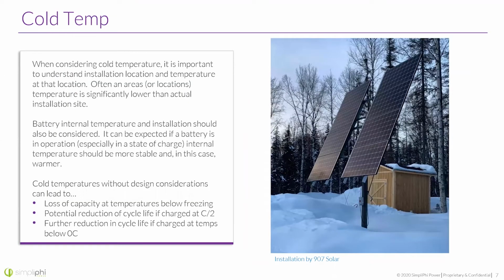So when considering cold temperature, it is important to understand installation location and temperature at the location. Often an area or location's temperature is significantly lower than the actual installation site. That's always where I see hiccups, where a customer simply says, hey, I know the temperature in my area gets to, let's say, 20 degrees Fahrenheit. Well, you can still mitigate that as simply as asking, is it indoors? Is that indoor room maybe a little bit insulated? That's probably enough to deal with that maybe 10-degree gap that you might be worried about.